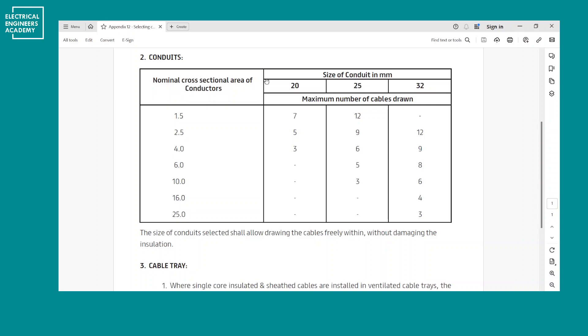To select the right conduit, you need to know what wires you're pulling through it. The table shows the nominal cross-sectional area of the conductor — for example, 1.5 or 2.5mm² — alongside the conduit diameter. For a 20mm conduit, you can pull a maximum of five 2.5mm² wires. In case you're using 4mm² wire, which is the nominal size for GPOs or power circuits, you can pull a maximum of three wires.